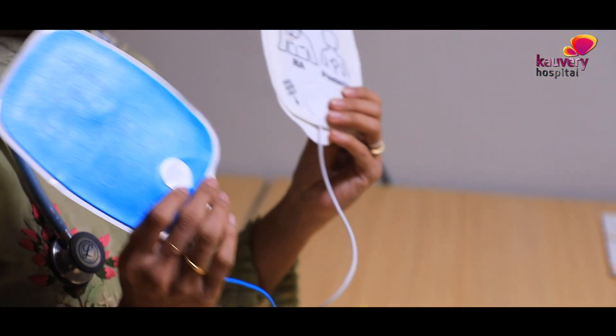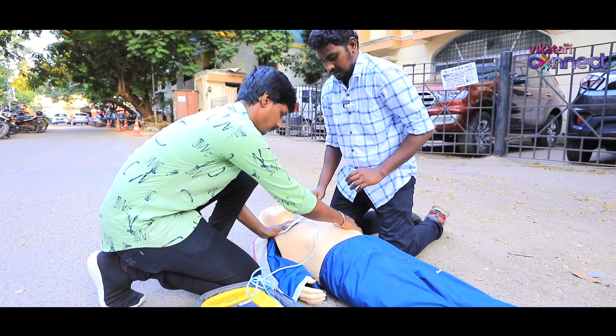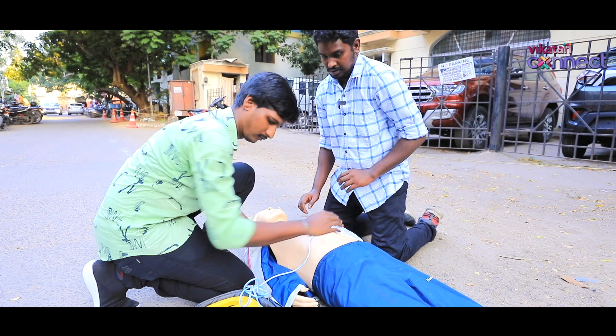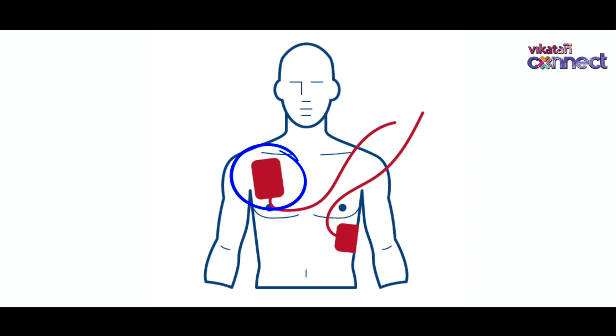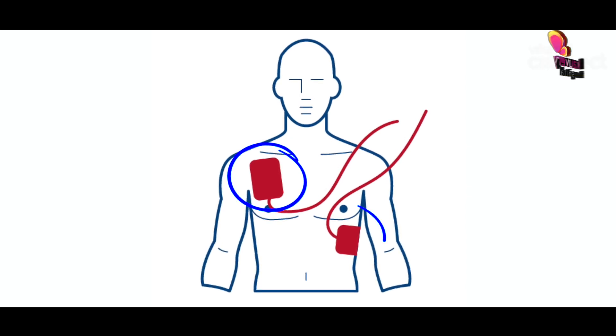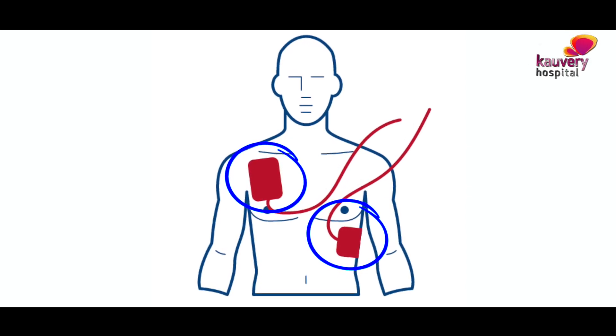This is an electrode pad applied to the patient's bare body. There are two pads in the adult size. In the hospital, there are also smaller pediatric pads for children. One pad is placed below the right collar bone, and the other pad is placed just below the left nipple.